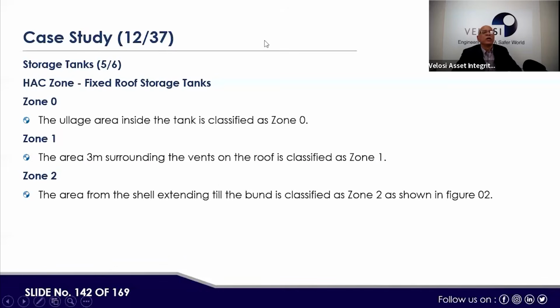Zone 0, the ullage area above the tank farm and the roof, fixed roof. This zone 0 is applicable on the fixed roof. The ullage area inside the tank is classified as zone 0. The area 3 meters around the vents on the roof is classified as zone 1. Then the area from the shell extended till the bund is classified as zone 2, shown in figure 2.